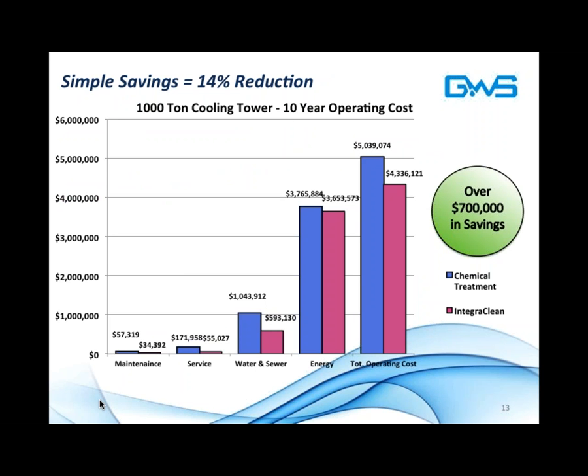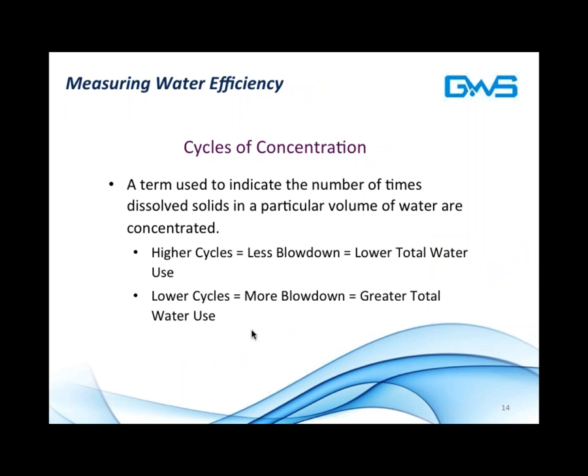From a financial standpoint, the simple savings here is about 14% in terms of total costs for the system. That equates to, in 10 years, about $700,000 in savings. This is without reusing that blowdown. So you can imagine that when you reuse the blowdown, the cost savings are enhanced significantly. Of course, the bulk of this, from a water and sewer standpoint, is in the difference. You can see my cursor on the screen between these two lines of the water and sewer graph. By operating the system more cleanly, you will eliminate inefficiencies attributed to scale buildup and biological growth in the system, and that will help support efficiency in the tower. So there are a lot of opportunities here for improving efficiency in cooling tower operation.